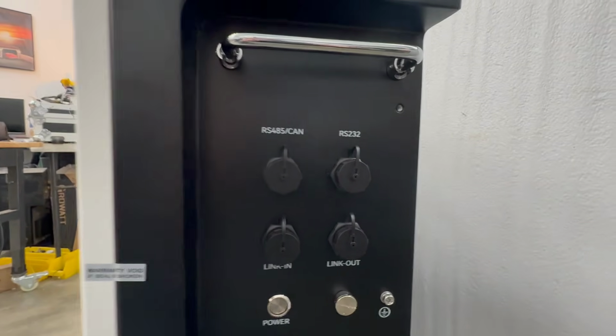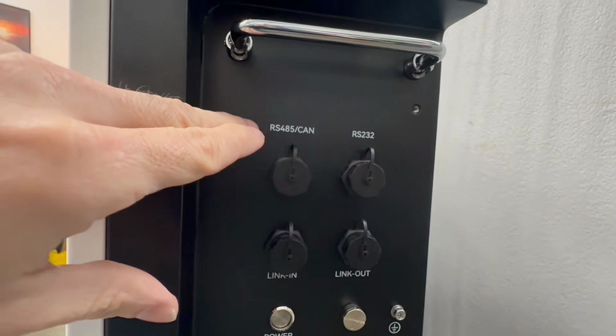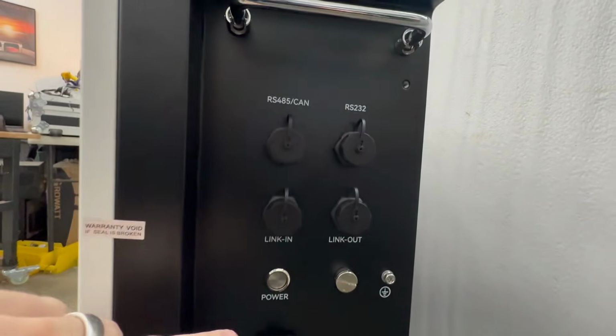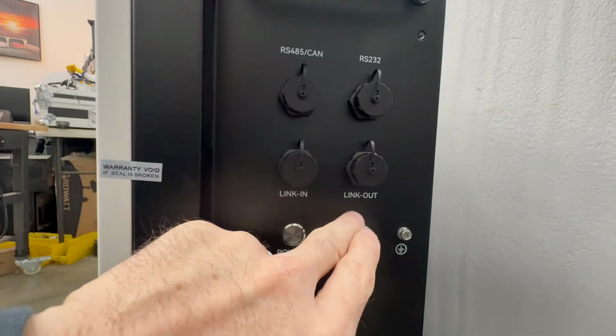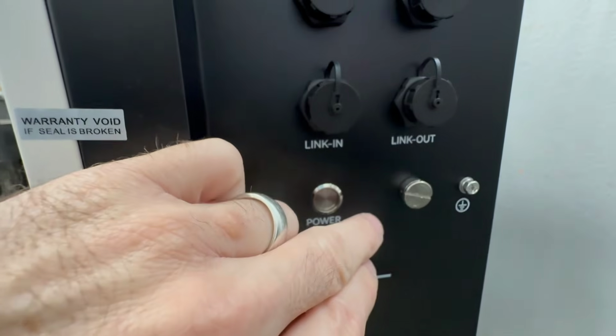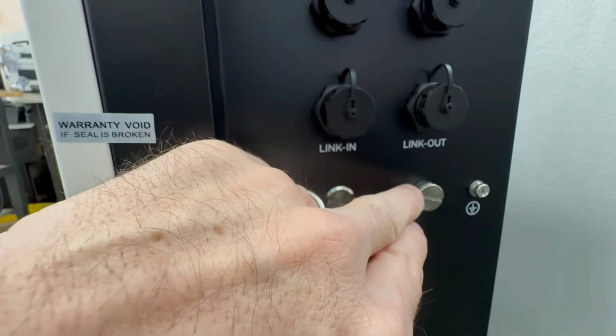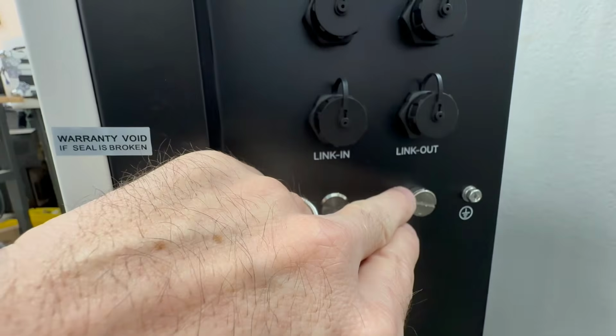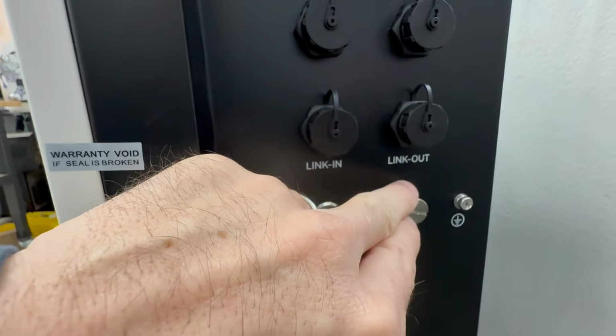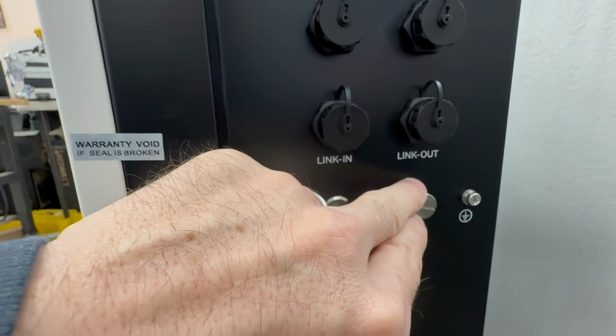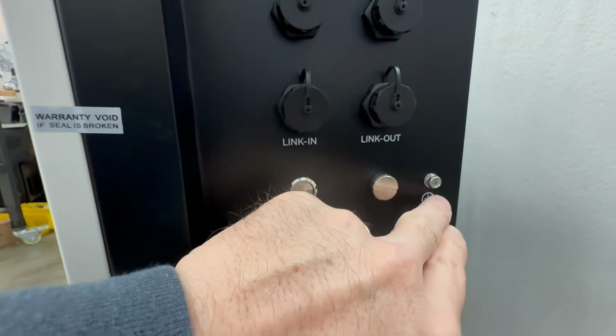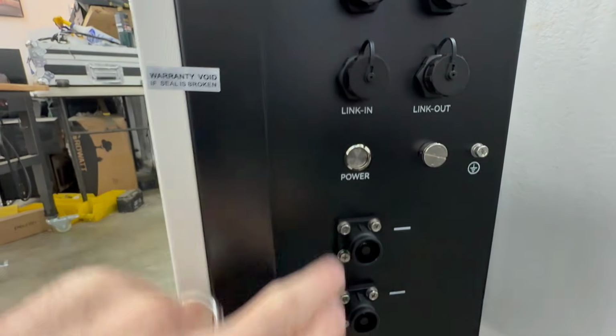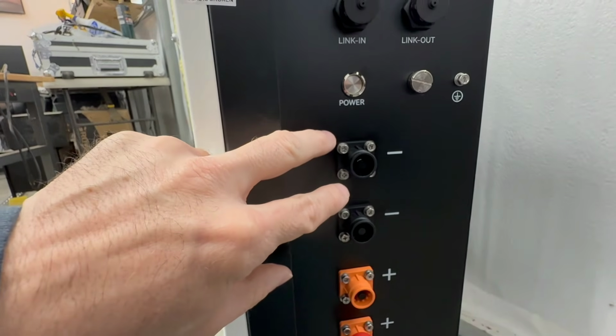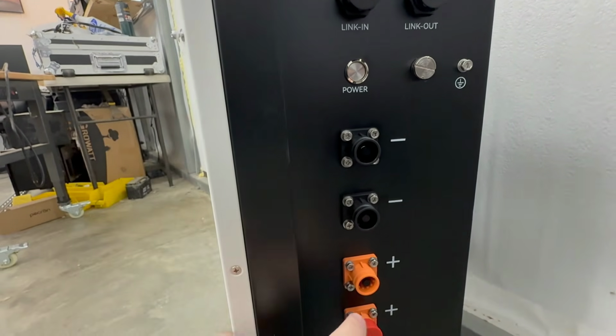On the side for connections, you can see it has RS-485, RS-232, link in and link out. It also has this vent on the side, so if there was a release of gas from one of the cells, the gas would be able to escape the metal case. You have your ground screw, your power button, and then a pair of negative and positive.